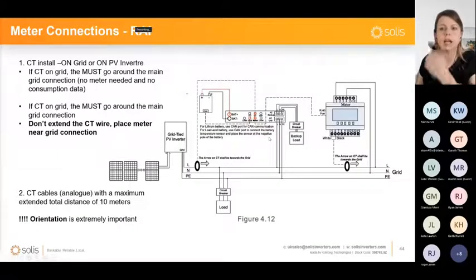For the RAI, the AC coupled one, they're almost the same, but there are a few differences. The first generation of the RAI that we distributed to the market did not actually have a meter. It only had a CT clamp. That CT clamp was installed on the main AC connection point and would feed information directly into the inverter, and based on that, the RAI would decide to charge or discharge the battery.